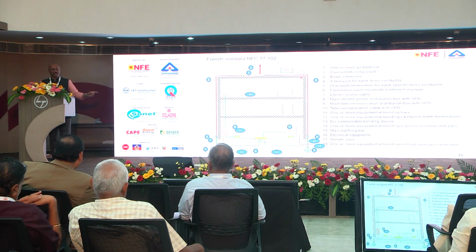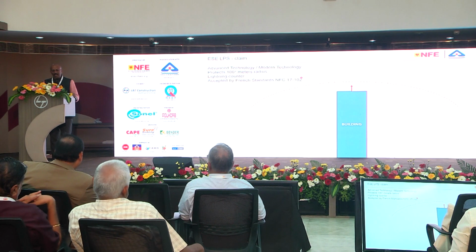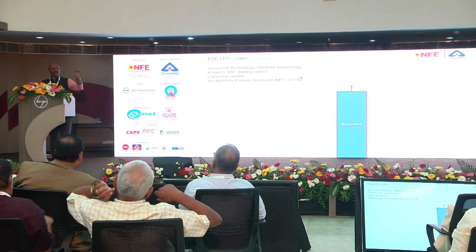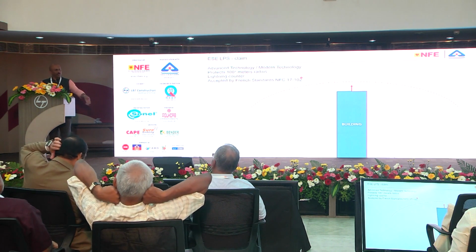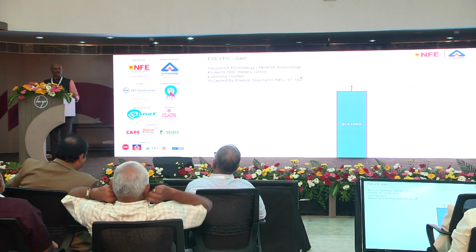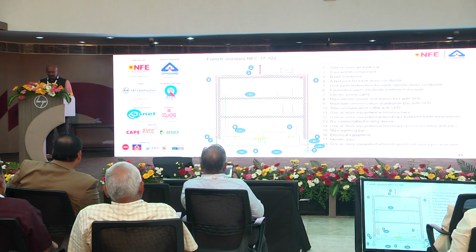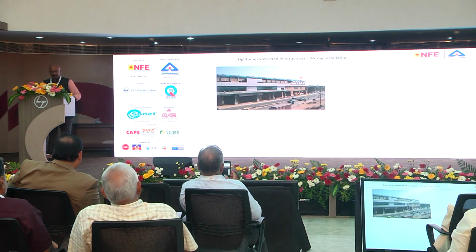But what is told in the Indian market? You have one rod, one down conductor and one earth electrode. Lightning will hit the rod and the current will flow like water flowing through a pipe and go to the soil. This story is absolutely wrong. So please understand it and try to follow.